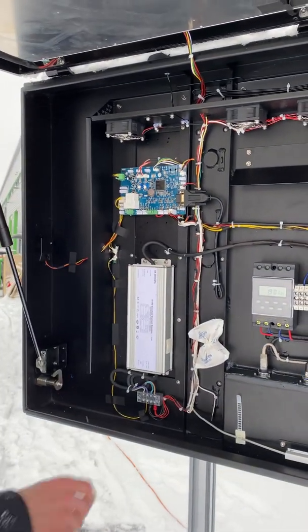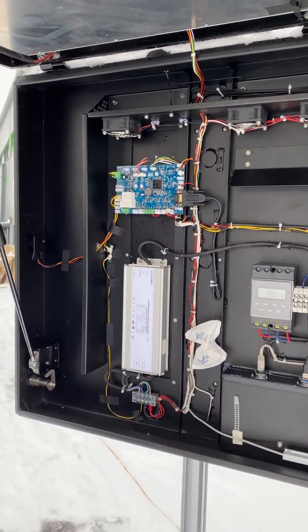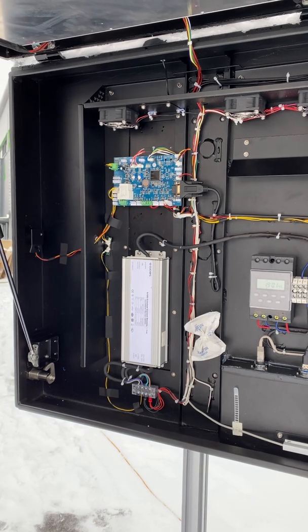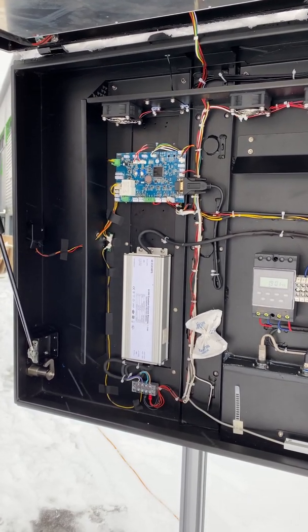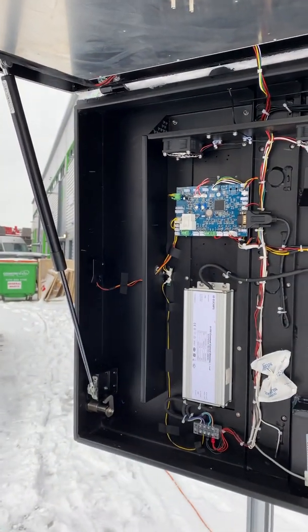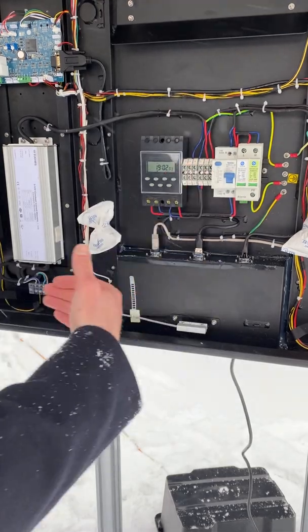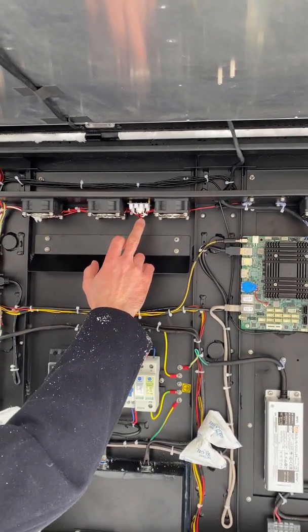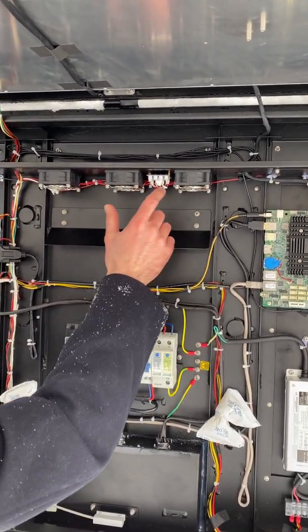Here we have the surveillance board, which is quite important on these outdoor systems to enable the customer to monitor performance when the system is installed in the field with no on-site presence. On this particular unit, we have several sensors included: a door sensor with a magnetic reed sensor to confirm the door is closed, a shock sensor for impact detection, and temperature sensors at the top and bottom of the unit to check for uniform temperature and confirm the fans are running. We also have a fan controller here which is sensing fan power and enabling fan speed control via the surveillance board.